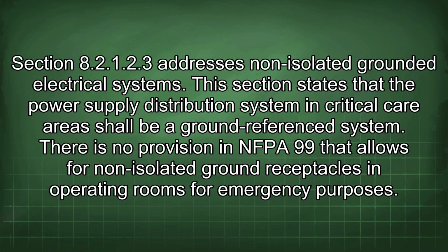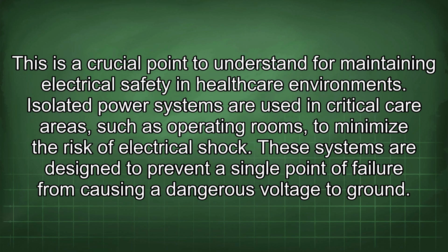There is no provision in NFPA 99 that allows for non-isolated ground receptacles in operating rooms for emergency purposes. This is a crucial point to understand for maintaining electrical safety in healthcare environments. Isolated power systems are used in critical care areas, such as operating rooms, to minimize the risk of electrical shock. These systems are designed to prevent a single point of failure from causing a dangerous voltage to ground.